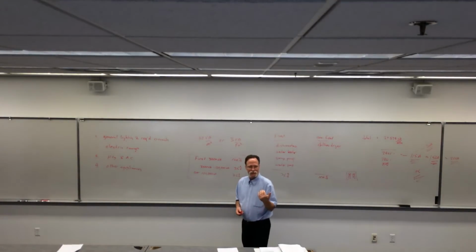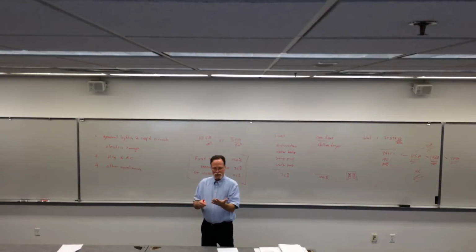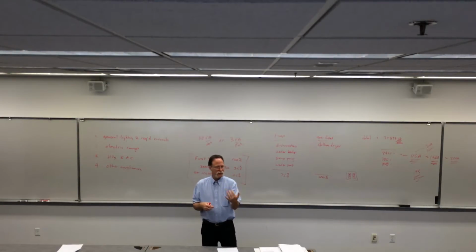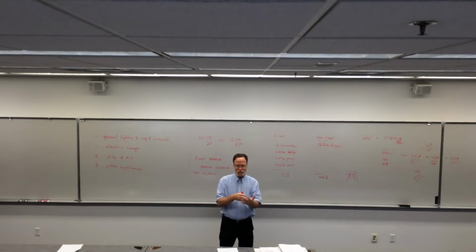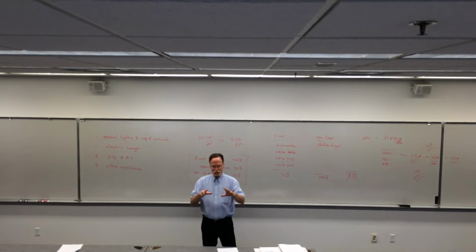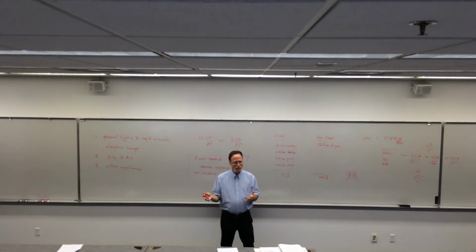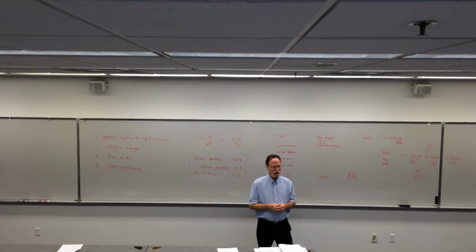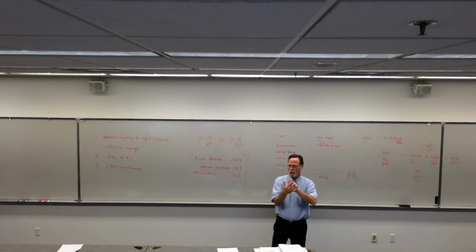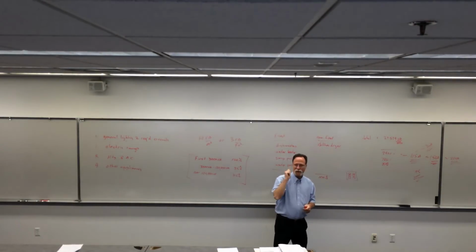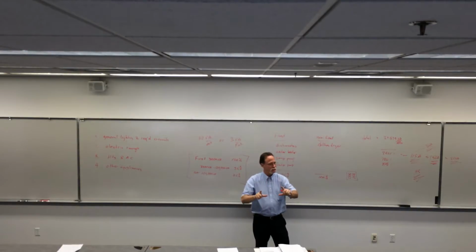There's a big complicated formula that says conductors of a certain size, if you have this many conductors coming in this box, and this many going out of a certain size, then that relates to the cubic inches of the box with this formula, and you have limits. When I said, well, I can cram that in, geez, I'll just be careful. And so you cram all the wires in a thin mount box because I didn't want the thicker box on my garage wall. And I didn't want to bang a hole in the concrete block and bury it in it.